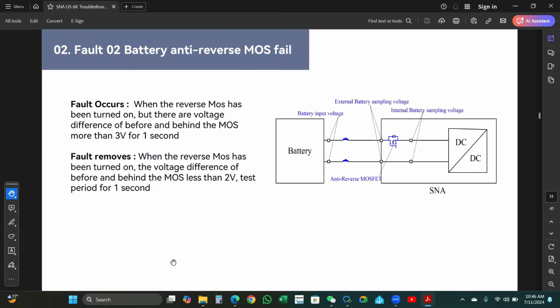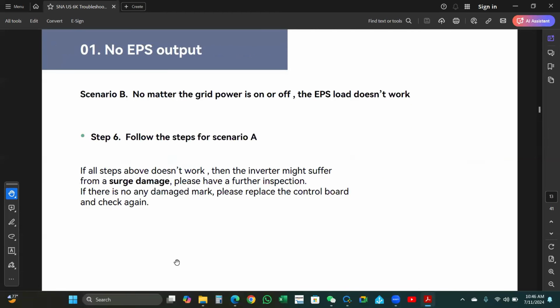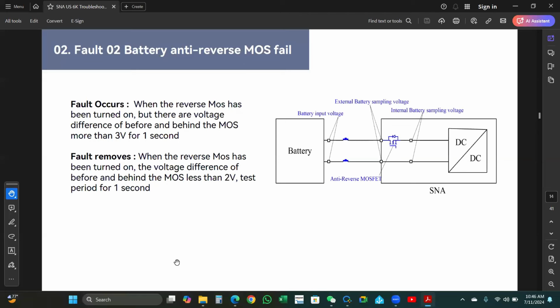Fault: battery anti-reverse MOS fail. The fault occurs when the reverse MOS has been turned on, but the voltage difference before and behind the MOS is more than 3 volts for 1 second. The fault is removed when the reverse MOS has been turned on and the voltage difference before and behind the MOS is less than 2 volts, with a test period of 1 second. This is a board inside the inverter.